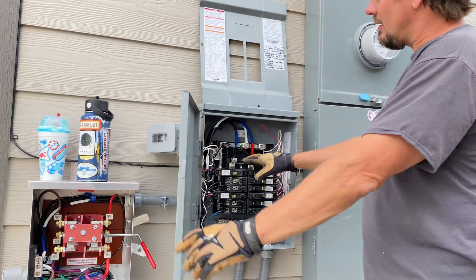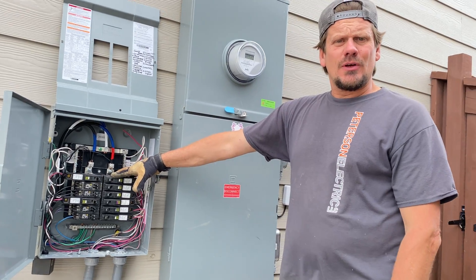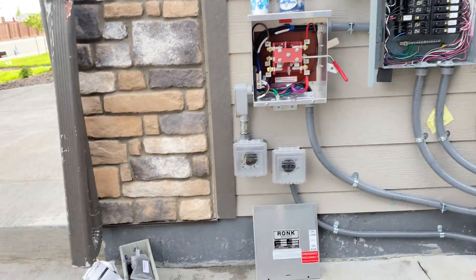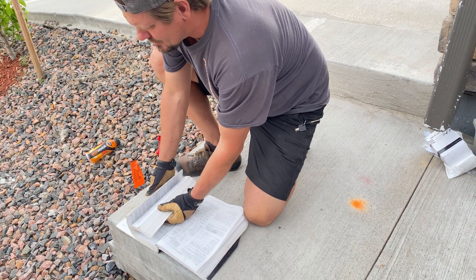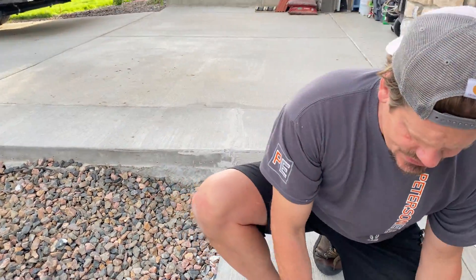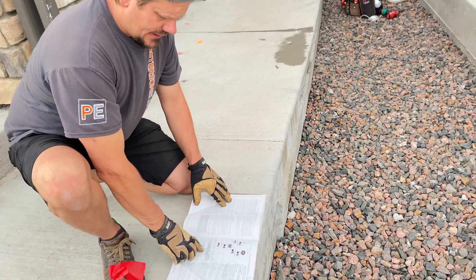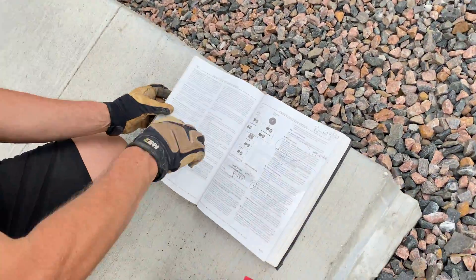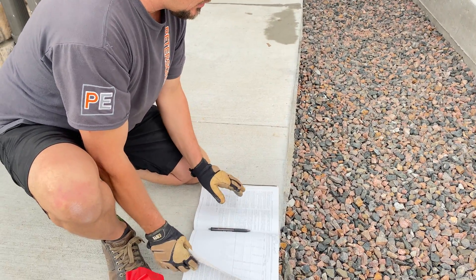When it's running it's not running that heavy of a load. I looked at NEC Article 220.42 and also Article 702. Article 702 is for optional standby systems — it's not a legally required system and it's a very small article. That also refers you to Article 445, which covers generators.